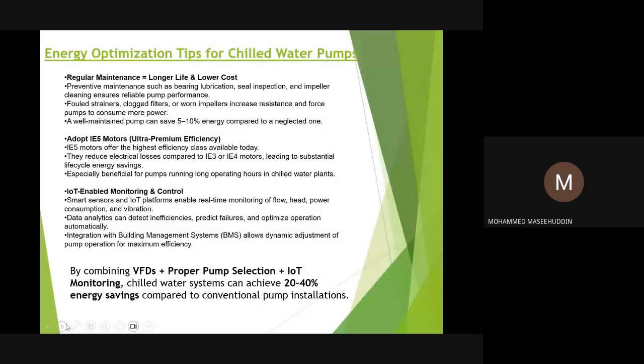And of course, the regular maintenance which is required for longer life and lower cost. But when it comes to regular maintenance, it doesn't mean again that we need to be near the pump or the pump room to do the maintenance. No, we can do this even remotely. As of today, we have IoT-enabled sensors and everything connected to the pumps, and we can use it from our mobile, from our offices or the laptops, and then we can just guide our technical team to go there and do the periodic maintenance by replacing the seals, or it could be bearings or shaft, etc.